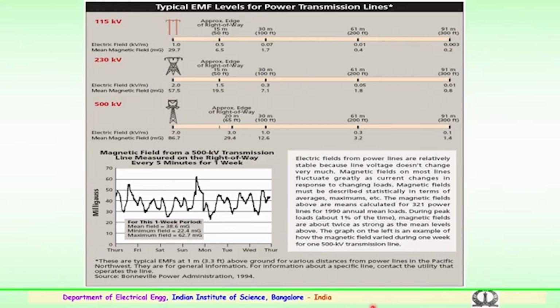Here are a few examples for various voltage levels, 115, 230 and 500 kilovolts. You see the towers, and the distance from the towers, and both the electric field in kV per meter and the magnetic field in milligauss, with the values clearly given here. Take the example of a 500 kV transmission system: you can see the electric field is 7 kV per meter at the midpoint of the tower, very near to the conductor.